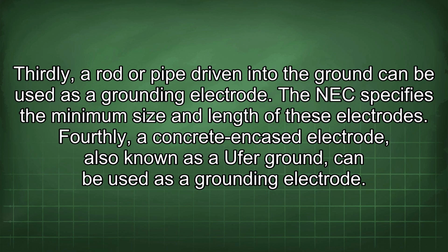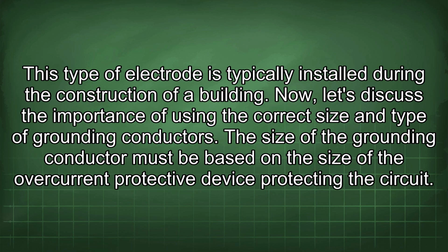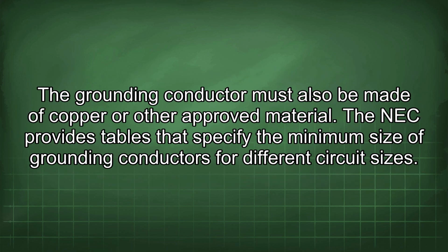Fourthly, a concrete encased electrode, also known as a Ufer ground, can be used as a grounding electrode. This type of electrode is typically installed during the construction of a building. Now, let's discuss the importance of using the correct size and type of grounding conductors. The size of the grounding conductor must be based on the size of the overcurrent protective device protecting the circuit. The grounding conductor must also be made of copper or other approved material. The NEC provides tables that specify the minimum size of grounding conductors for different circuit sizes.